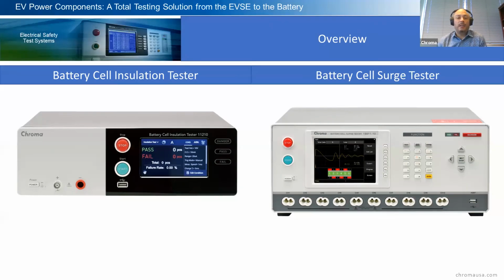The cell insulation tester is an instrument used for measuring leakage current and insulation resistance of a battery jelly roll or dry cell, as well as some other insulation materials. Let's just stick to those two. Besides the standard LC and IR, which is leakage current and insulation resistance measurement, we also have a unique function called partial discharge or flashover that may have occurred inside the insulation material during the high voltage insulation testing process. So what does this mean?